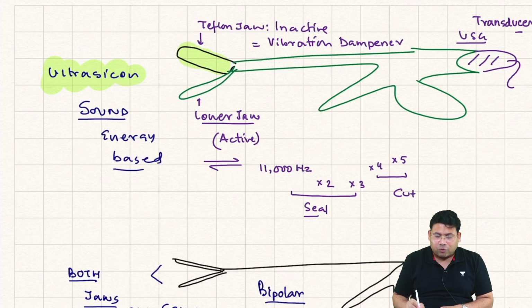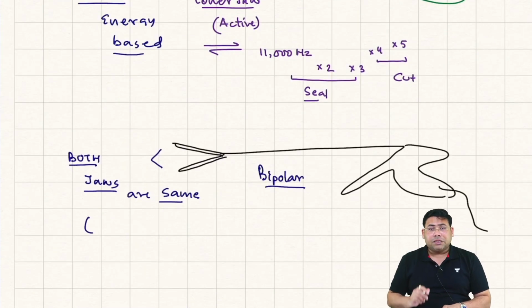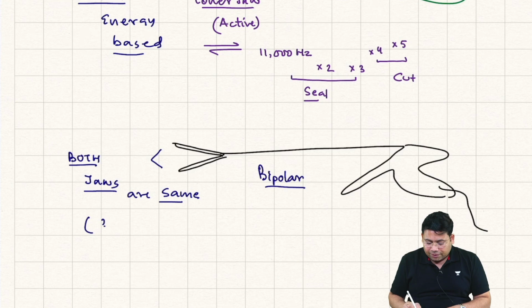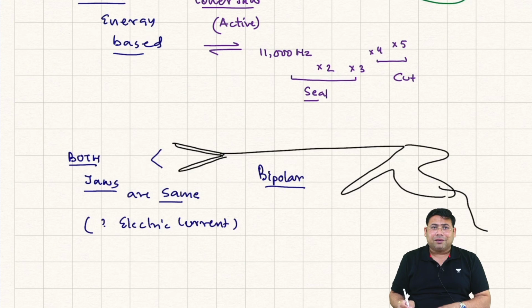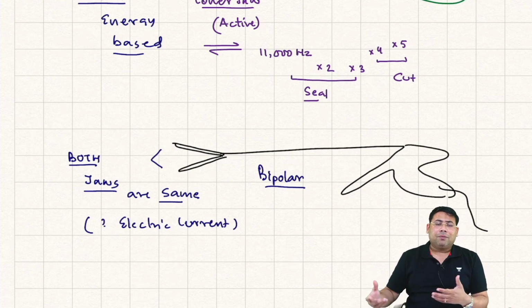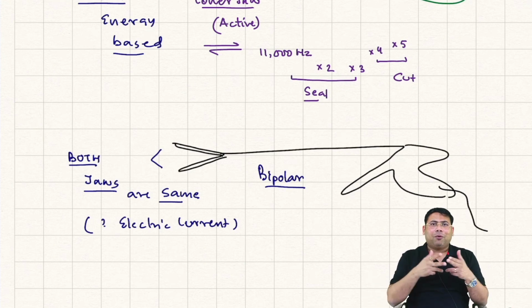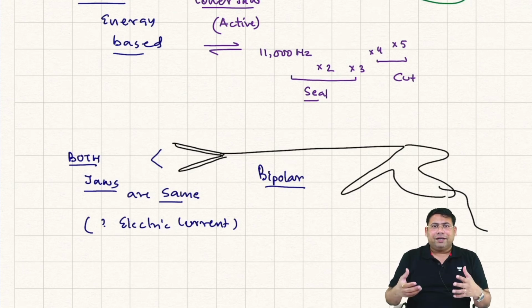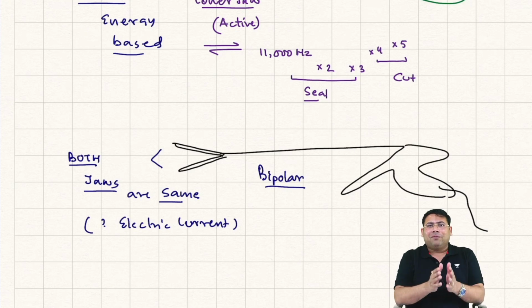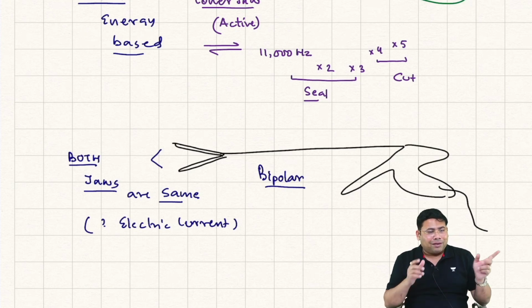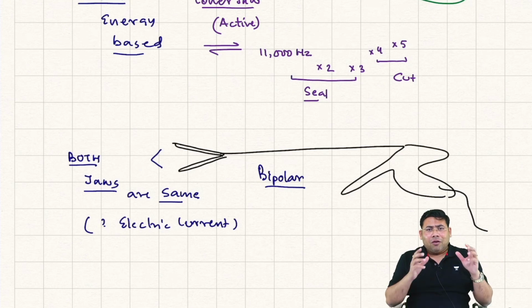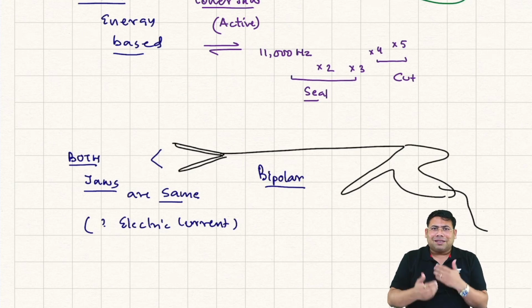Whereas when you talk about this technology, this is very, very important. This is the concept based on electric current. So it's electric current based. The only difference between this bipolar and a conventional bipolar is that in conventional bipolar, if you keep on heating the tissue, it will heat. Once a scar is formed, and if you reheat a scar, there is a charcoal formation, and the charcoal will get dislodged and rebleeding will occur. But this has a tissue moisture sensor. Once the moisture is desiccated off, it will cut off the cycle, and once it cuts off the cycle, the current will not flow through this.